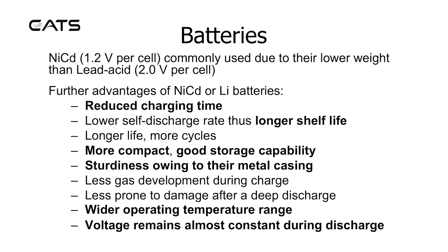Further advantages of NiCAD or lithium batteries are: reduced charging time, lower self-discharge rate thus longer shelf life, longer life with more cycles, more compact with good storage capability, sturdiness owing to their metal casing, less gas development during charge, less prone to damage after a deep discharge, a wider operating temperature range, and the voltage remains almost constant during discharge.